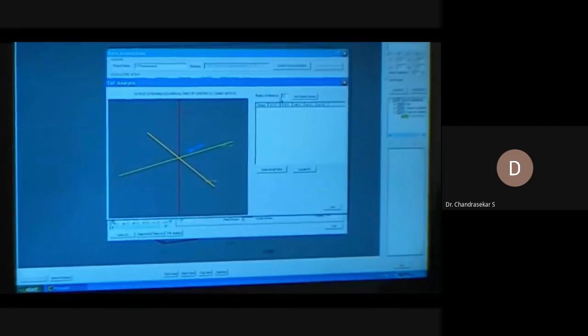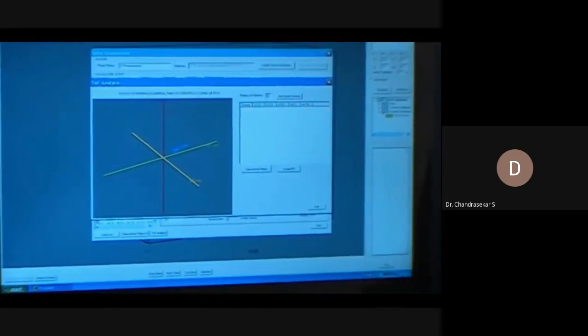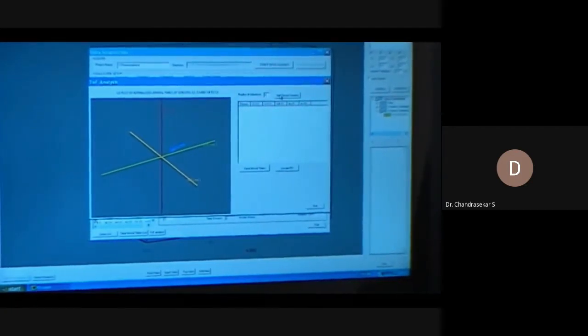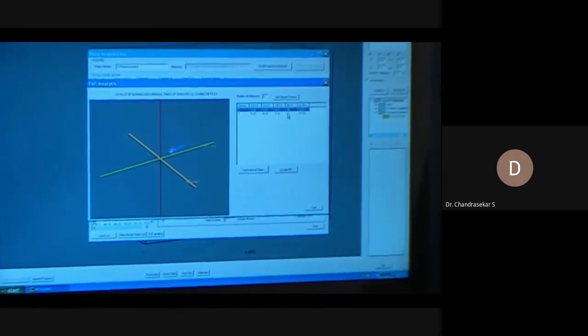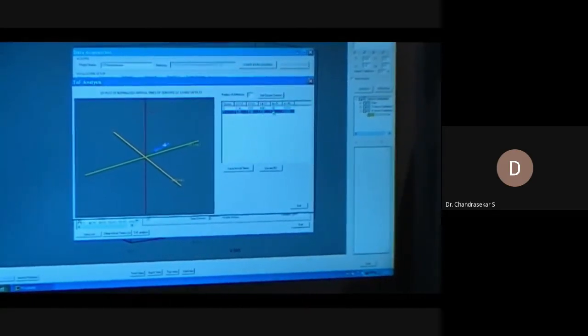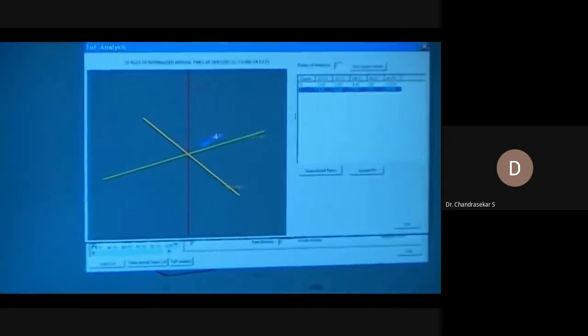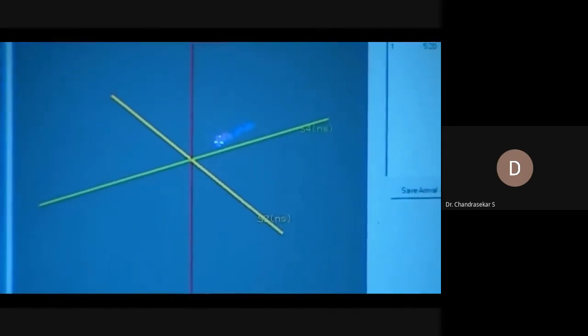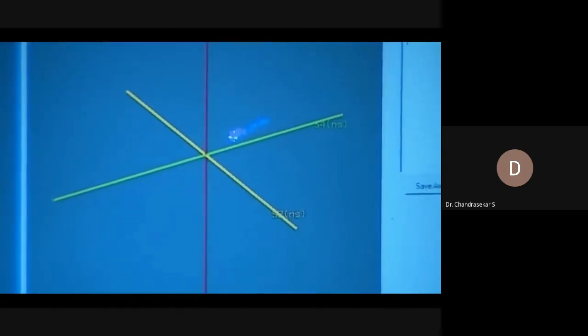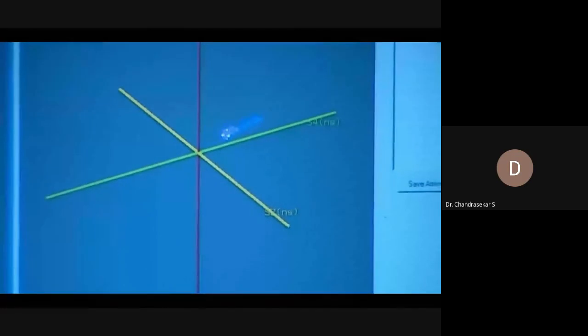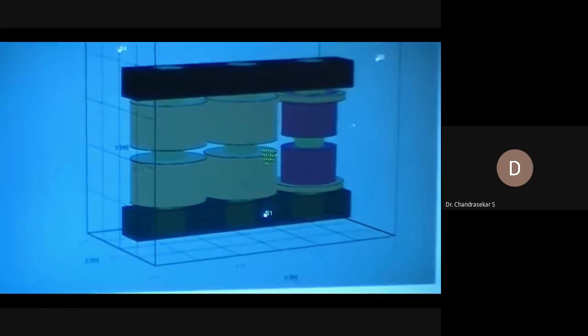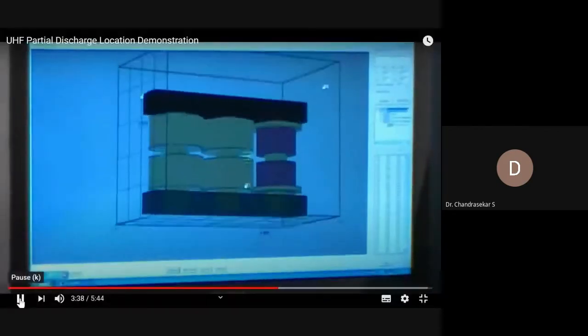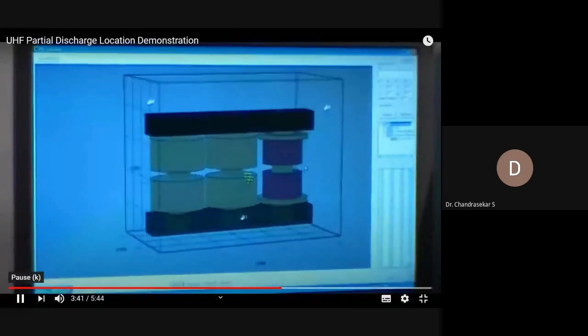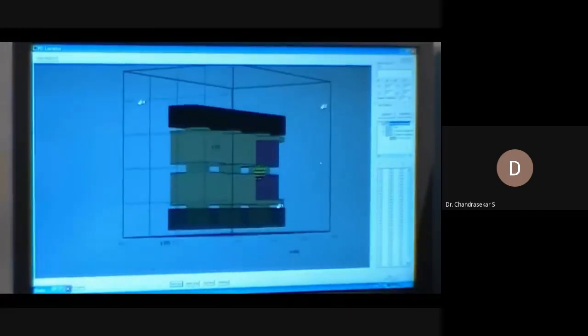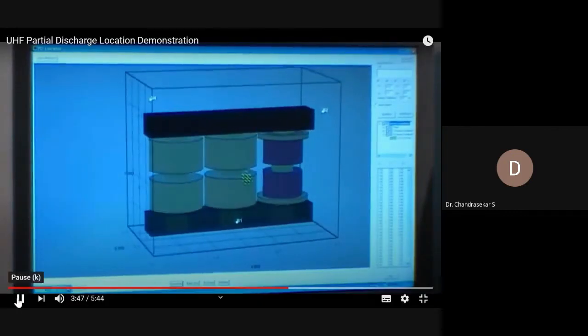Now we can define a certain clustering tolerance to pick out where the real bunches of data are within this data. And we can see here is one where there are 56 points accumulated in that part of the data set, whereas there are only 11 in this part of the data set. So we select this one, all those arrival times get averaged to give us the best time of flight, and then if we click locate PD, it feeds those times through into the system here, and you can see that the cluster, which is based on a tolerance of 0.5 nanoseconds, is right in the center of the middle winding where the spark is indeed located.